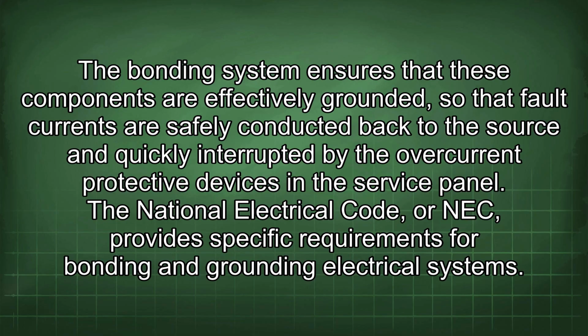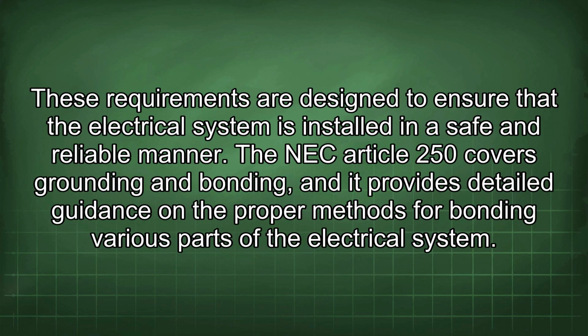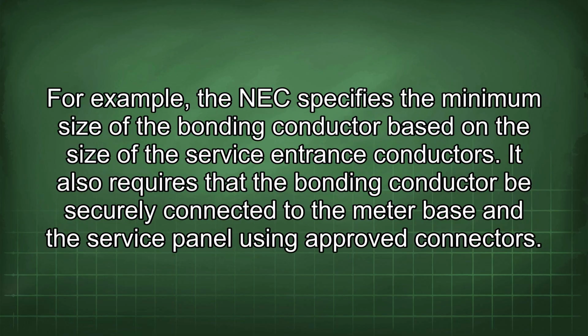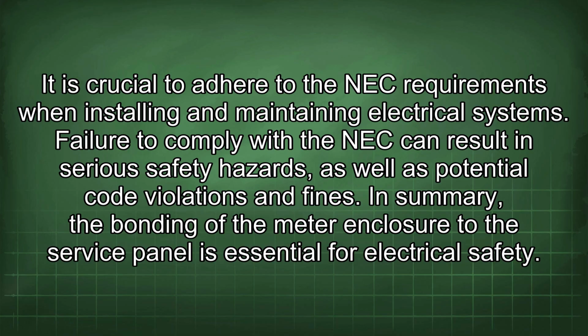The National Electrical Code, or NEC, provides specific requirements for bonding and grounding electrical systems. These requirements are designed to ensure that the electrical system is installed in a safe and reliable manner. The NEC Article 250 covers grounding and bonding, and it provides detailed guidance on the proper methods for bonding various parts of the electrical system. For example, the NEC specifies the minimum size of the bonding conductor based on the size of the service entrance conductors. It also requires that the bonding conductor be securely connected to the meter base and the service panel using approved connectors. It is crucial to adhere to the NEC requirements when installing and maintaining electrical systems. Failure to comply with the NEC can result in serious safety hazards, as well as potential code violations and fines.